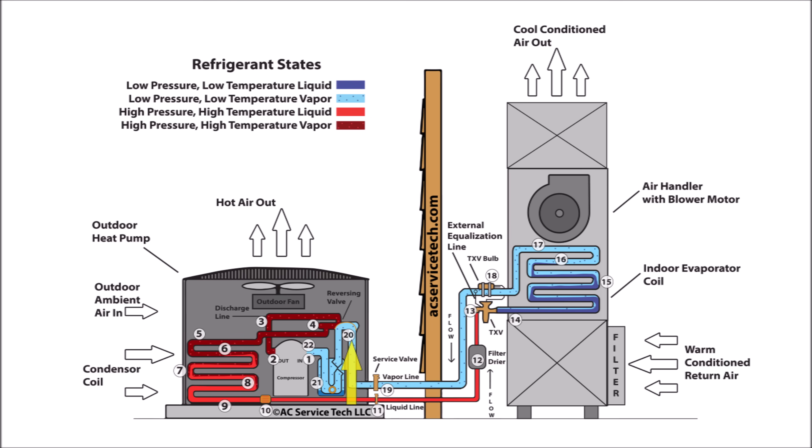In step twenty, you have the low pressure, low temperature, superheated vapor traveling through the reversing valve and into the accumulator tank. In step twenty-one, the vapor travels through the accumulator, whose job is to protect the compressor by preventing any unwanted liquid from entering the compressor inlet. At the bottom of the accumulator tank, there's an oil return metering device that allows oil and any liquid refrigerant gathered there to re-enter the vapor line. Any liquid refrigerant that enters that metering device quickly gets flashed into a saturated state and turns into vapor before reaching the compressor. Typically in air conditioning mode, there's not much liquid in the accumulator tank, but in heating mode, there may be some liquid refrigerant present.